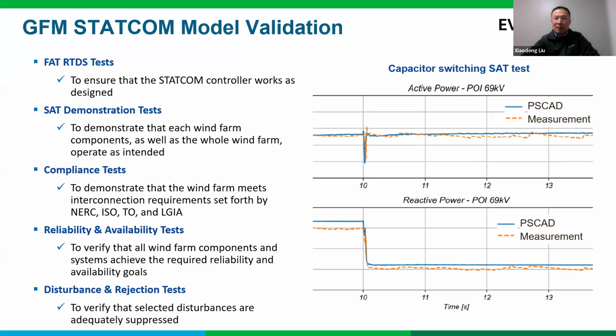There are some other tests, the compliance test, to confirm that the wind farm meets all kinds of technical requirements set by NERC, ISO, TO, or interconnection requirements. The reliability test is also very important to verify the reliability of the wind farm over an extended time period, for example, 200 hours of continuous operation. We know that there are plenty of things which can't be modeled, for example, the cooling system of the STATCOM. So it is important to know its performance and if it operates reliably, right?